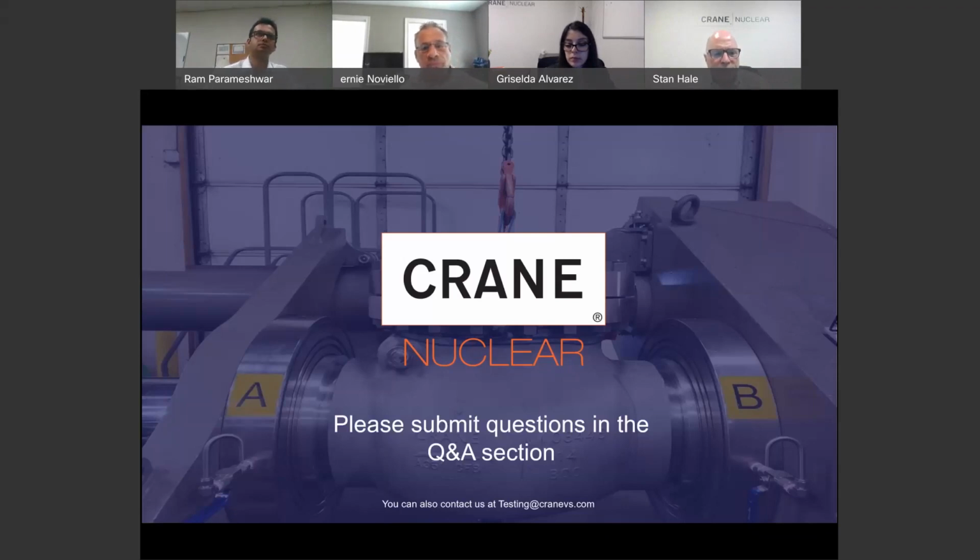I can help you a little bit here, Ernie. Acoustic emission leak detection is different from the acoustic vibration testing that we're doing with check valves. The acoustic vibration testing we're doing is much lower frequency. It's down at 25 kilohertz or less, mostly in the audible range. If you're using acoustic emission for leak testing, like has been used in some of the Appendix J test programs, that's a different type of transducer.